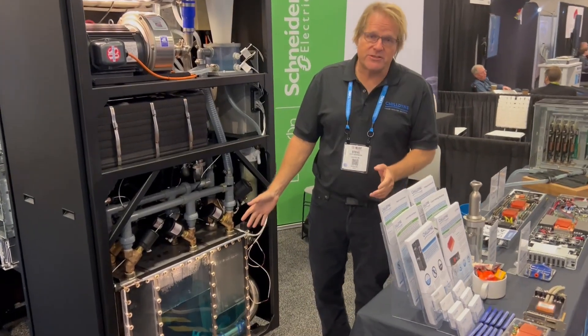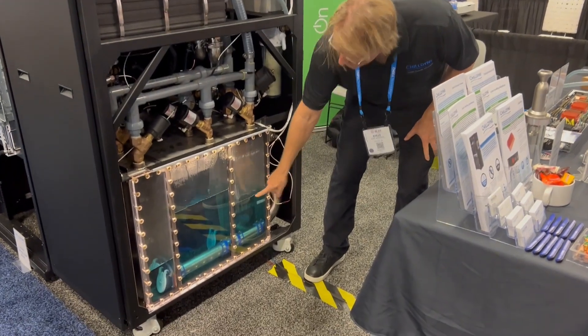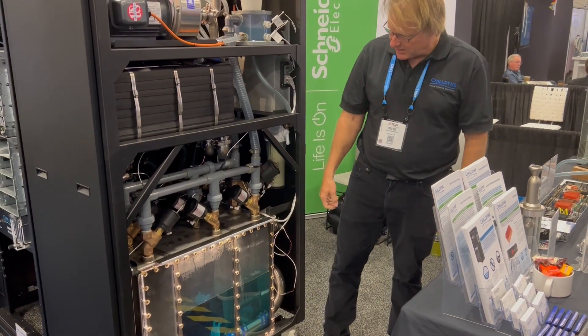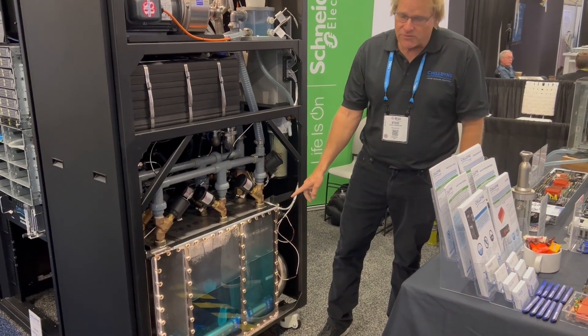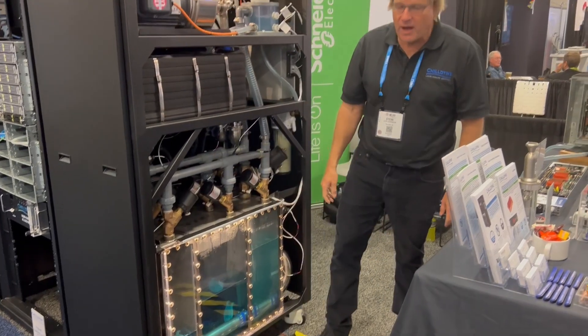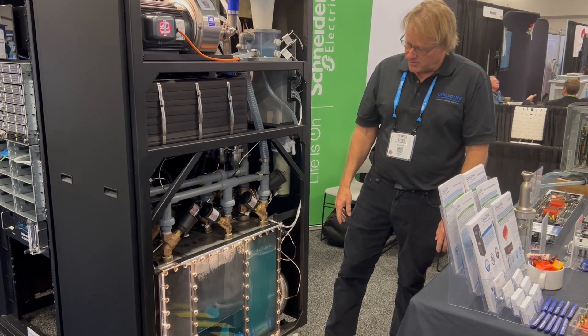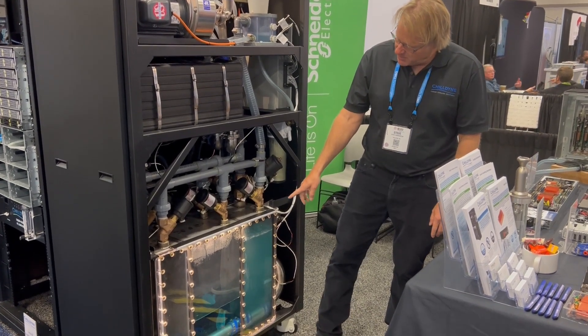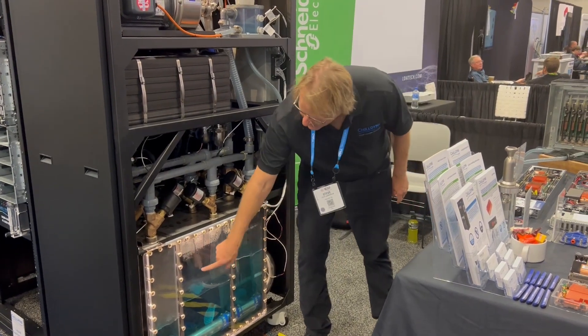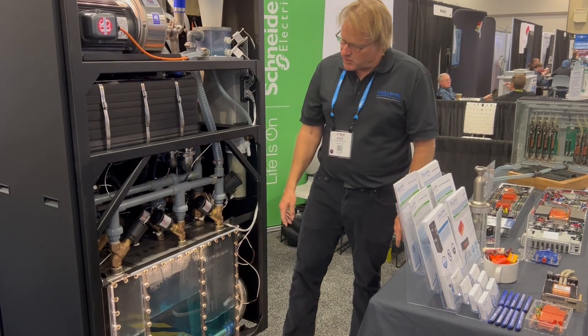This is Chilldyne's negative pressure CDU. How it works is we apply vacuum to a pump chamber and pull the water through the server and into the CDU. When this pump chamber reaches a full level, we apply vacuum to the other pump chamber and start pulling on that. That way we have continuous flow through the server, and each time a pump chamber gets full it dumps into a reservoir. Our reservoir supplies the server with coolant that has been cooled.